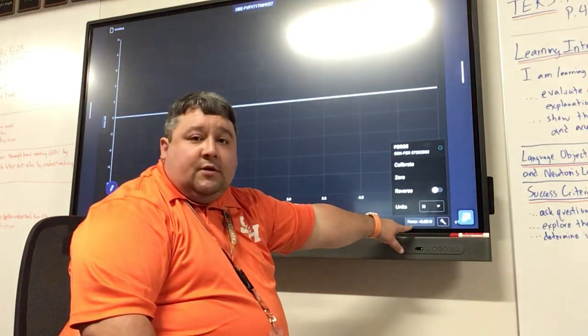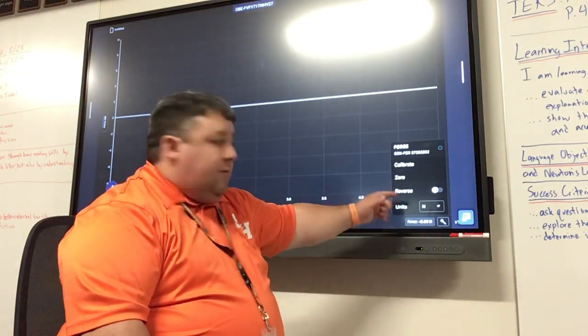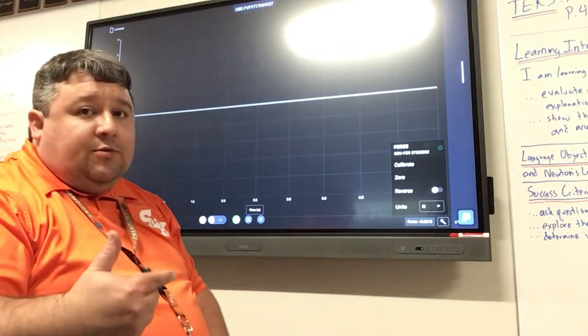If there's two sensors attached here, you'll have two options here. When you click on one, it will show you that. And make sure that the one you're calibrating is the one you're holding in your hand as you're actually doing the calibration.